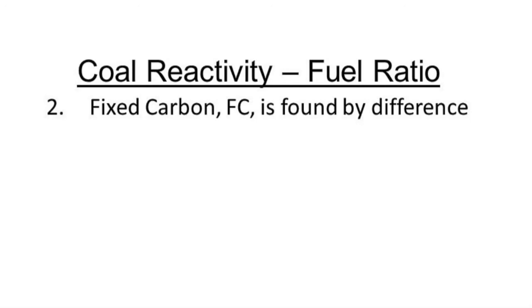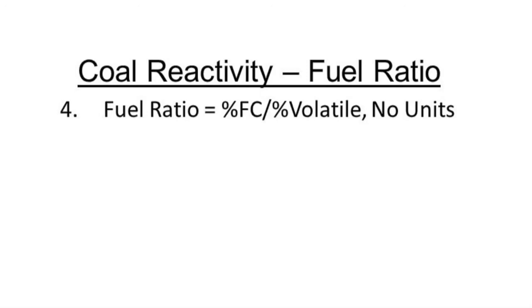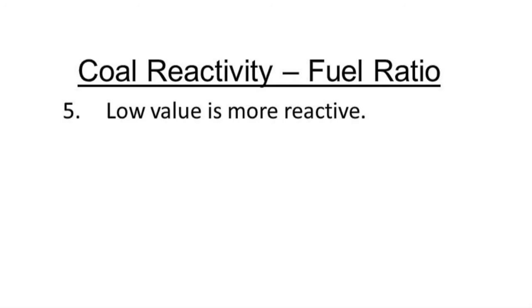The errors in fixed carbon could be two, three, or four percent, so keep in mind that the fixed carbon value can have some error associated with it — it's not as strong a number as the direct measurement of volatile. Because the fuel ratio is fixed carbon divided by volatile, both measured in percent, the percents cancel out and the fuel ratio is just a dimensionless value, usually around one or two. It's the low values of fuel ratio that indicate more reactive coals, so if you want to create confusion, tell people that one is more reactive than one-and-a-half — and unfortunately that's what you have to do with the fuel ratio.